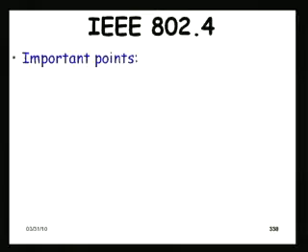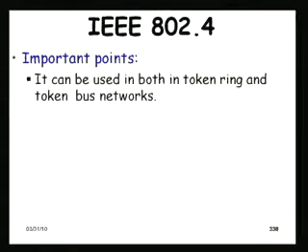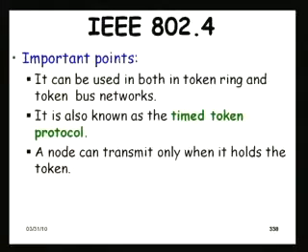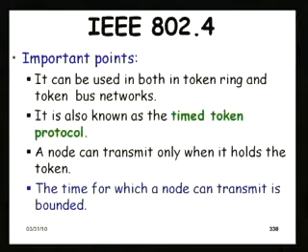Some important points in the working of the protocol are that it is used either in a token ring or a token bus network, and these have a special advantage in manufacturing situations and have been in use in manufacturing automation for quite some time. The 802.4 is also popularly known as the timed token protocol. A node is allowed to transmit only when it is in possession of the token. The token visits every node and only when a node holds the token can it transmit, and once it starts transmitting the duration for which it can transmit is bounded.